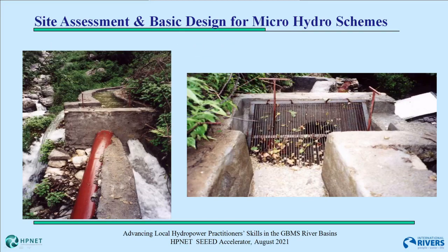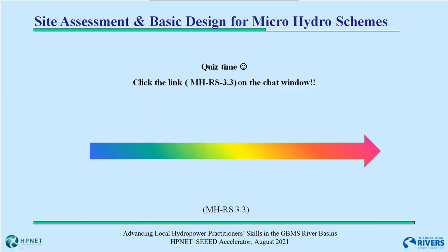This slide shows a simple and effective forebay design. It has a trash rack, which stops small stones and other debris getting into the penstock. There are 2 simple valves, one to open up the flushing, the other one is to divert the water to the canal downstream to stop the turbine.